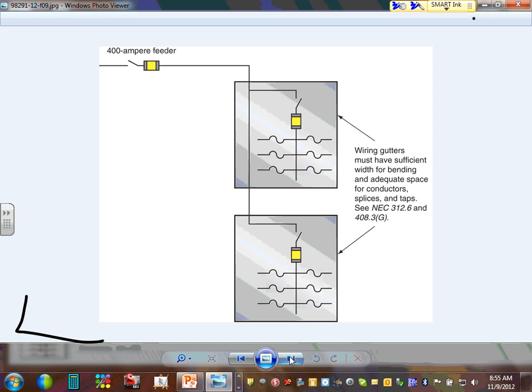You can feed circuit breakers. This is not feed-through. This is called subfeed. You guys remember when Jerry was here and he talked about subfeed? This is your subfeed. You have 400 amp and you feed 200 amp here and you feed another 200 amp here. Subfeed. So you bring the feeder here, can you guys see? After you bring the feeder to the disconnect, you tap the feeder and you come back and you feed another panel. And you're moving inside the panel.